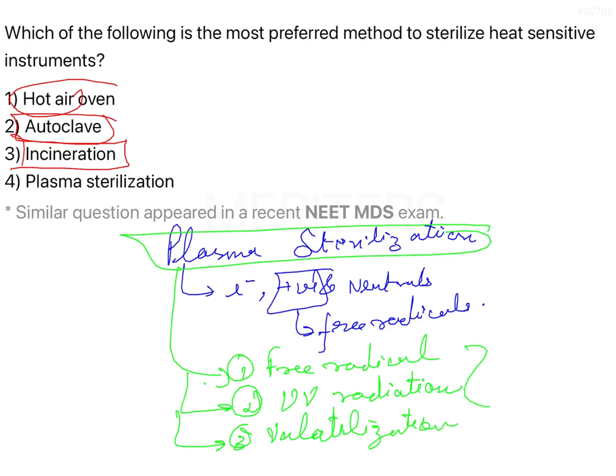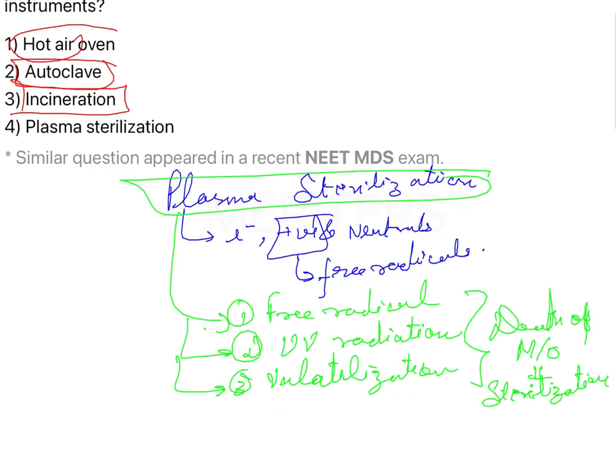These three mechanisms cause the death of microorganisms and achieve sterilization — that is why we call it plasma sterilization. Looking at gas plasma sterilization specifically, it involves the use of hydrogen peroxide — H2O2 plasma sterilization, also called hydrogen peroxide sterilization.